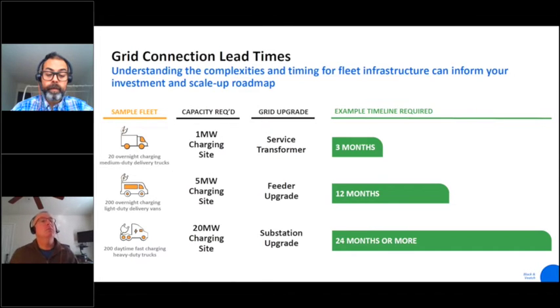Starting to get larger, into something in the 5 megawatt range, you're going to start looking at a feeder upgrade, which is basically a new line coming into your facility, with the appropriate timeline. When you get to the 20 megawatt phase of capacity, you're really going to start looking at substations. For the layperson, substations are those big gray boxes, surrounded by fencing, that take transformers, switches, and circuit protectors, and are a big investment on behalf of the utility. That's easily going to take 2 years or more to get in place.